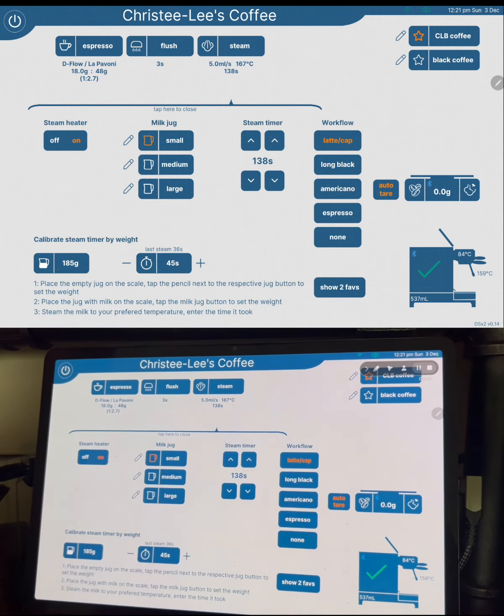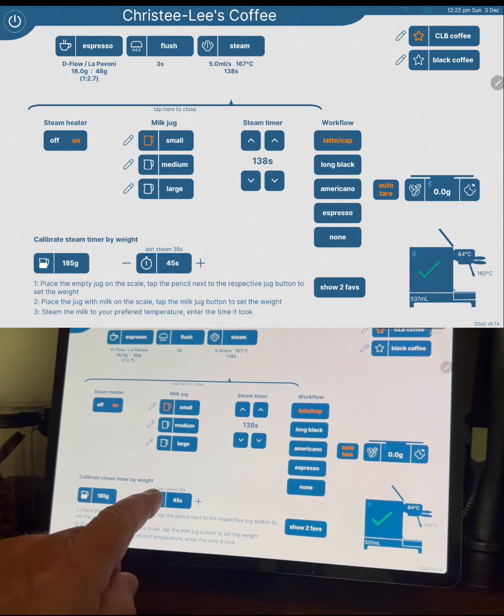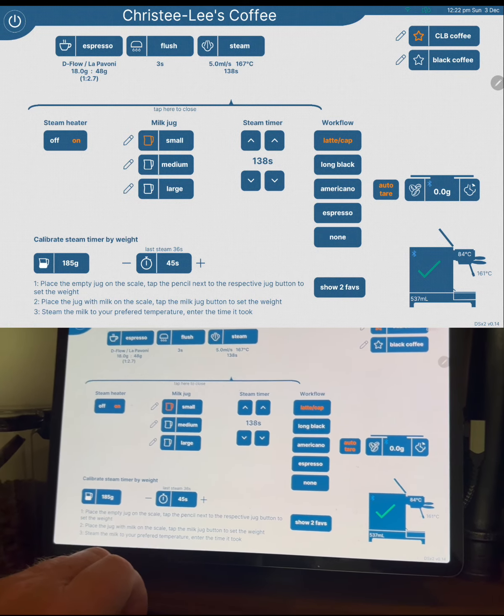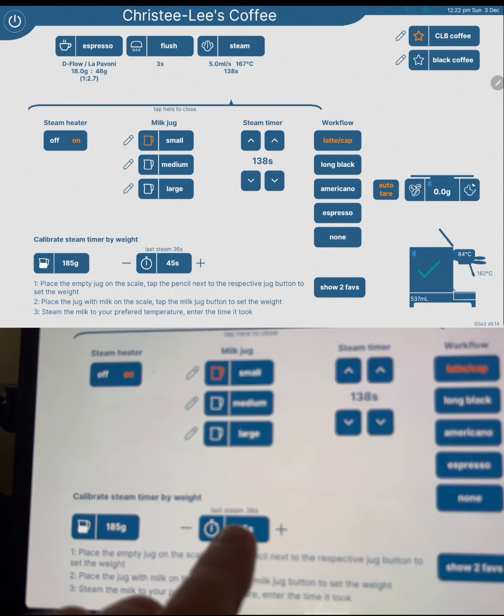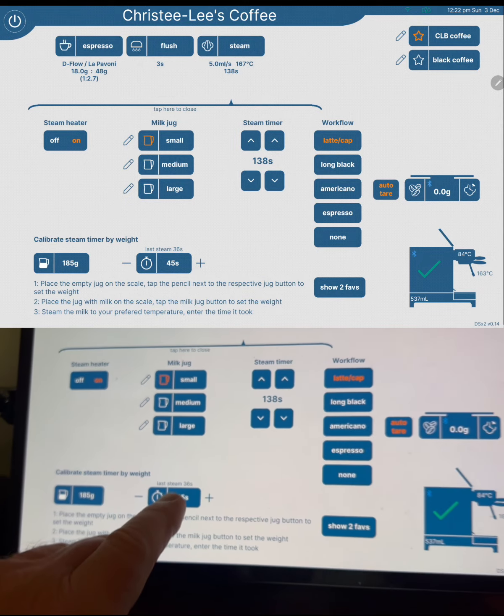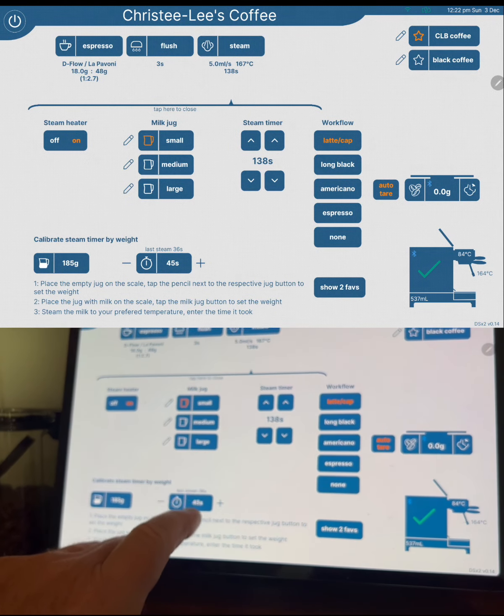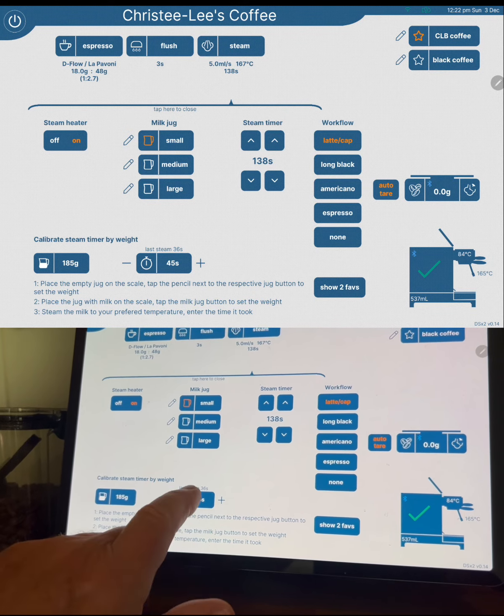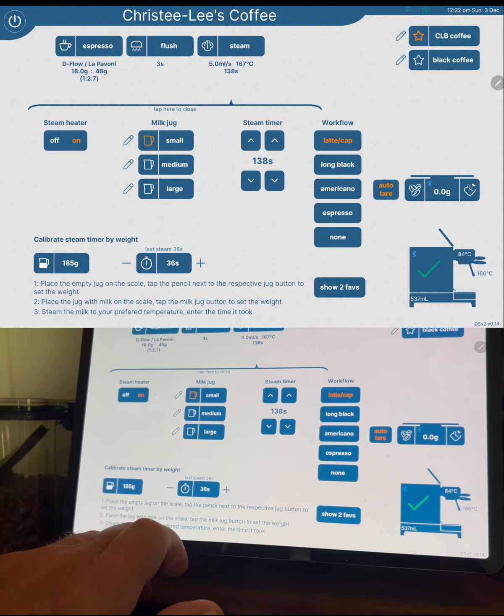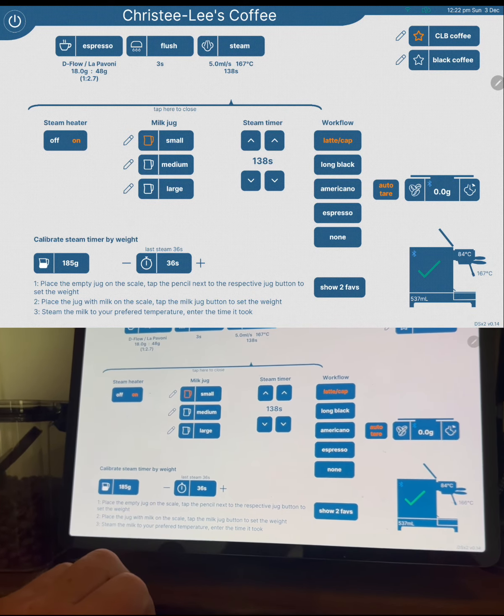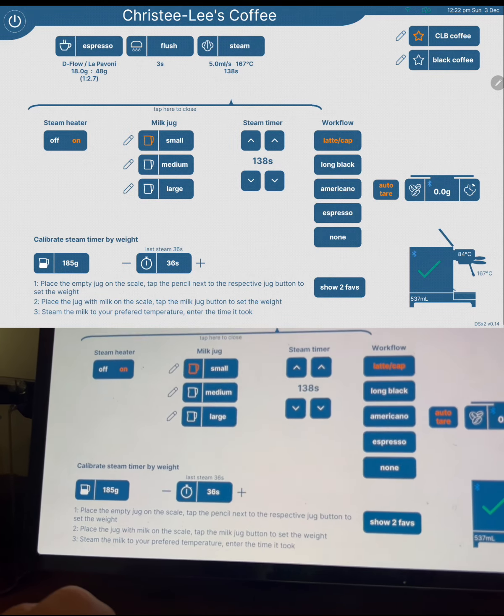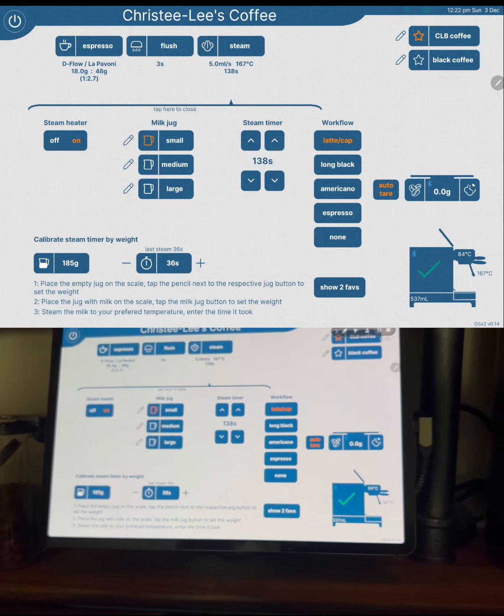Now I'll go back into settings, and you can see my last steam time was 36 seconds. All I need to do is tap this button in the middle, and that updates the calibration setting to our last steam time. So I'll tap on there — now it's set to 36 seconds, and our calibration is finished.